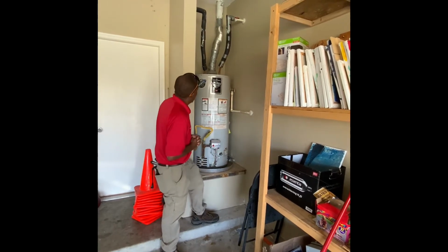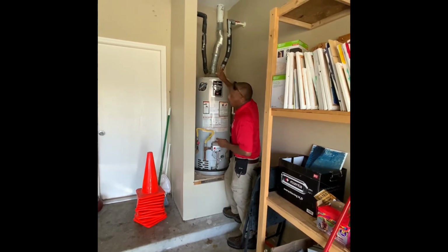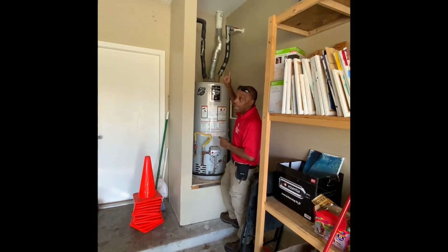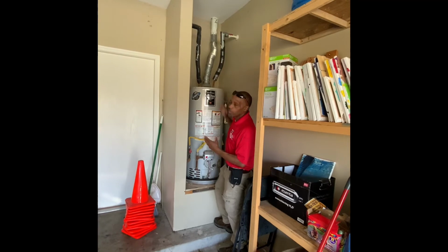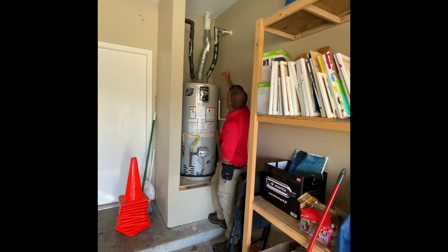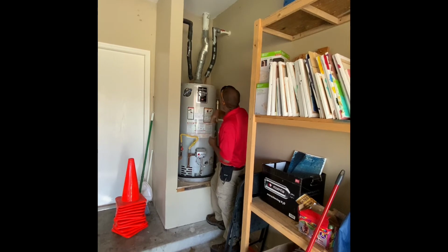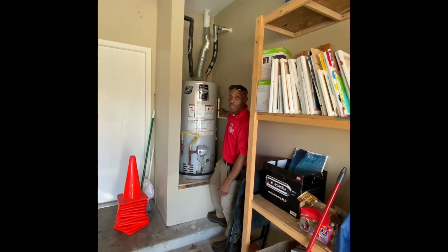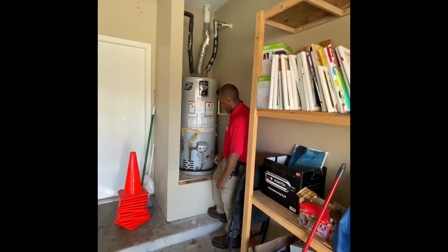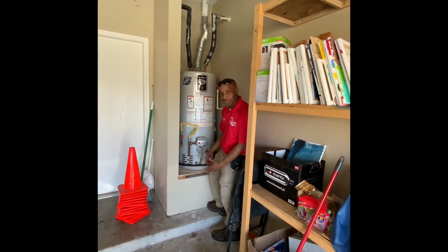So we're looking to make sure you have the proper piping and that it drains to a safe location. We're also looking at vent piping for your CO gases, and we go through the attic to make sure that this particular venting doesn't vent inside the attic; it should vent through the roof. So we're looking at the condition of the vent piping and the material as well, and also your incoming cold water and your hot water. You should not have a valve located on this temperature pressure relief valve. There should be no valves whatsoever on that. And we're looking that you have a drain pan as well, and the condition of the drain pan.